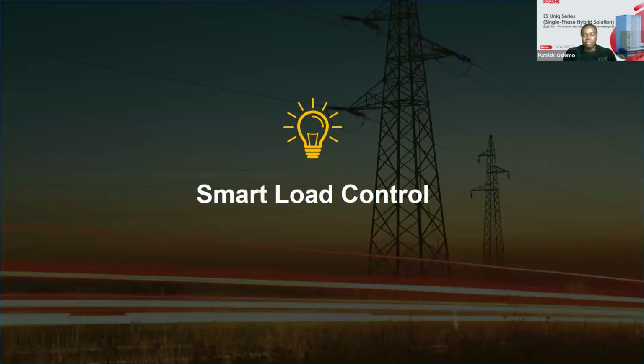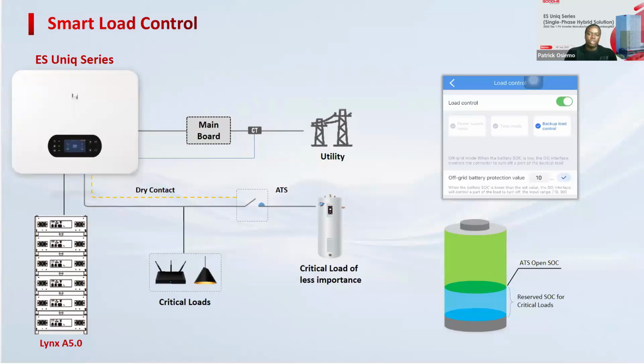Now, the next point is how smart your system should be. We're now moving into smart home technology. GoodWe boasts of providing a smart home solution, and this is one of the points that we're offering. The ES Uniq also comes with smart load control. In the sense that if you have big load-consumption appliances, for example heat pumps, and your grid is not available, you are running on your batteries. You will not want to fully drain your batteries because you want to use your heat pumps. The system can be set up automatically, or you can use a timing mode, or you can switch off particular loads manually.